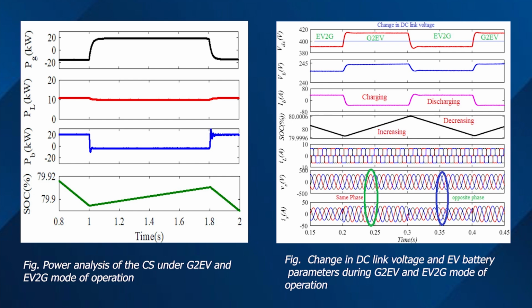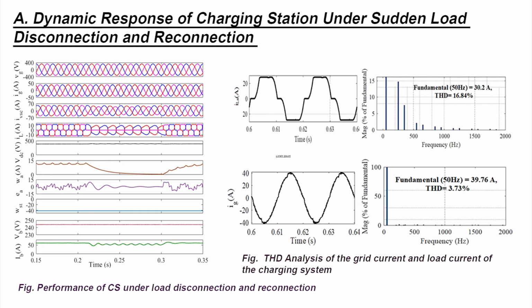This is the dynamic performance of the charging stations, where one of the phases is removed. Suppose there is single phasing, or one single phase onboard charger is connected and the other phase is removed, or there is no power requirement from the other phase, so how will the currents and voltage of the grid behave?